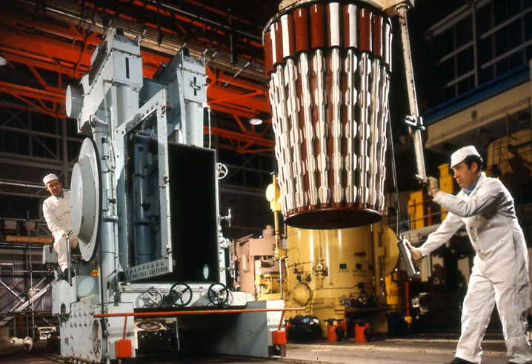Once removed from the reactor, the used fuel elements are stored in cooling ponds — with the exception of Wylfa, which has dry stores in a carbon dioxide atmosphere where the decay heat is transferred to the pond water, and then removed by the pond water circulation, cooling and filtration system. The fact that fuel elements can only be stored for a limited period in water before the Magnox cladding deteriorates, and must therefore inevitably be reprocessed, added to the costs of the Magnox program. Later reviews criticized the continuing development project by project instead of standardization on the most economical design, and for persisting with the development of a reactor which achieved only two export orders. A retrospective evaluation of costs, using a low 5% discount rate on capital, estimated Magnox electricity costs were nearly 50% higher than coal power stations would have provided.